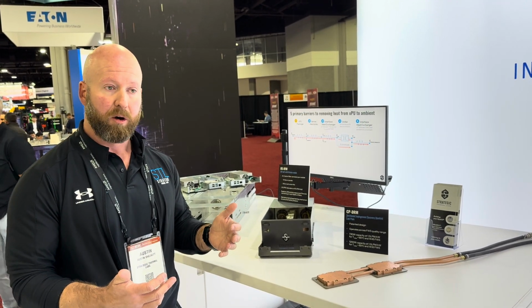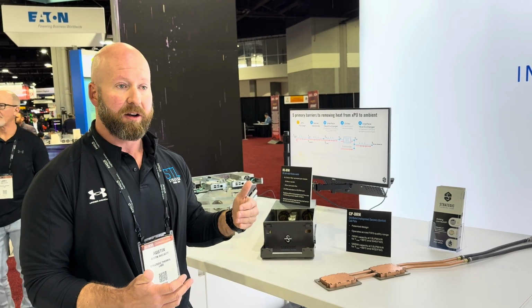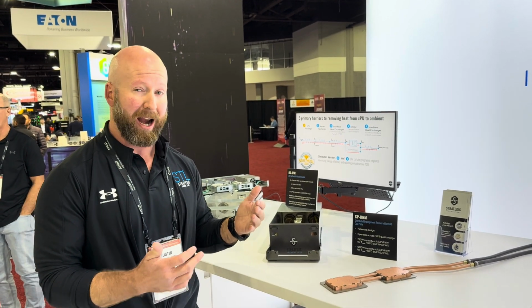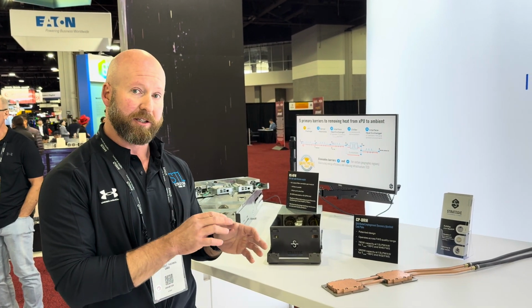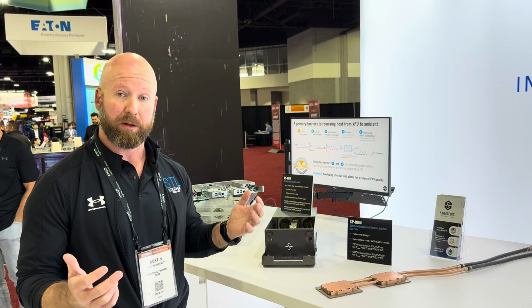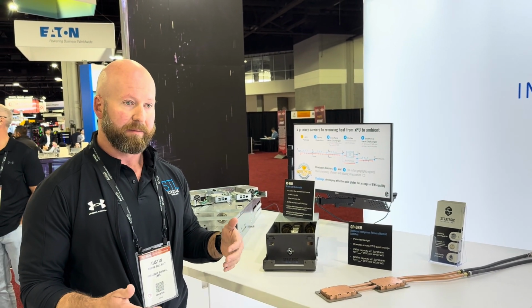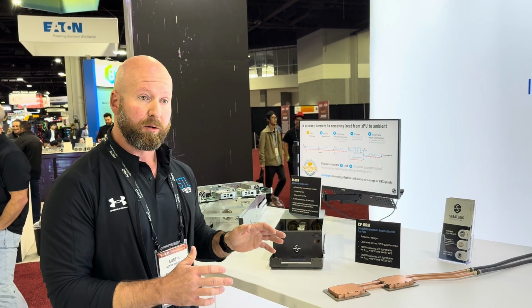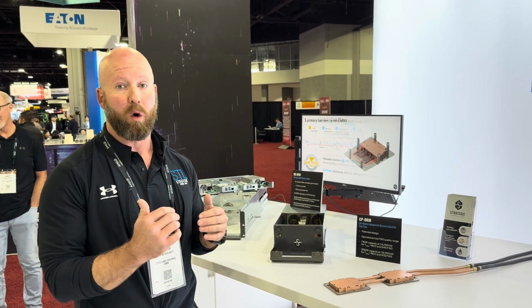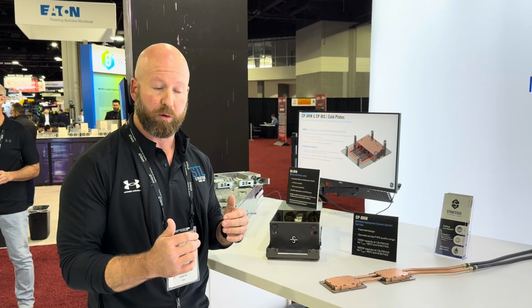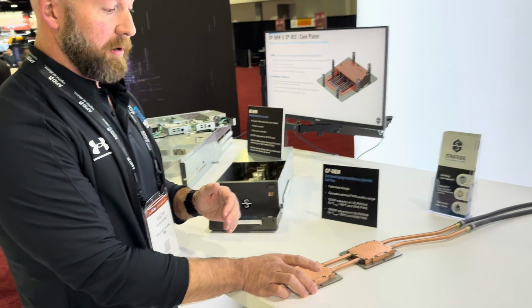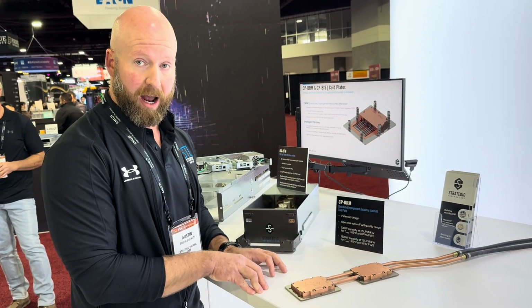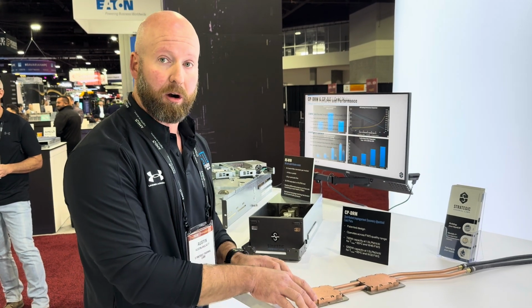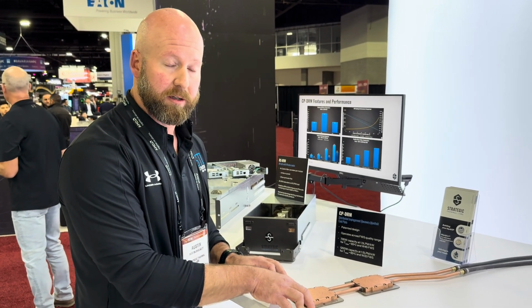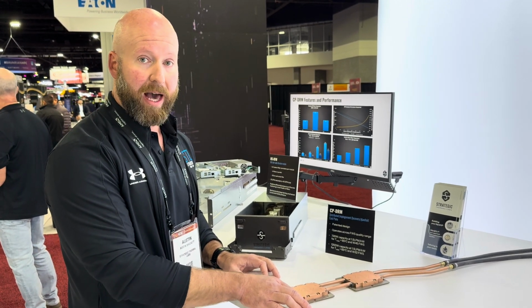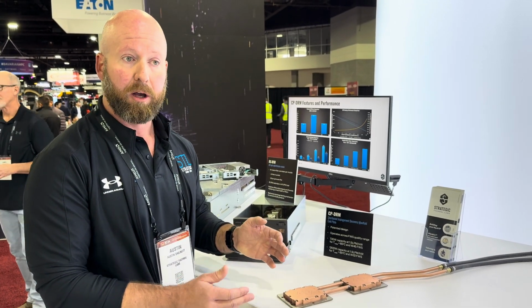We believe that the CDU, while a necessary component of liquid cooling today, ultimately represents a fairly large thermodynamic parasite in the thermal resistance stack from a processor to the outside air. Our goal at Stream Thermal Labs is to eliminate thermal resistances, and from a thermodynamic perspective, getting rid of the CDU has significant benefits for being able to increase water temperature in the building and increase energy efficiency in the building as well. So this cold plate was designed using our distributed impingement recovery manifold technology, which allows us to create a much larger channel with a hydraulic diameter of 600 microns and allow facility water to move through it freely without causing any long-term degradation issues that might possibly occur with a more sensitive cold plate.